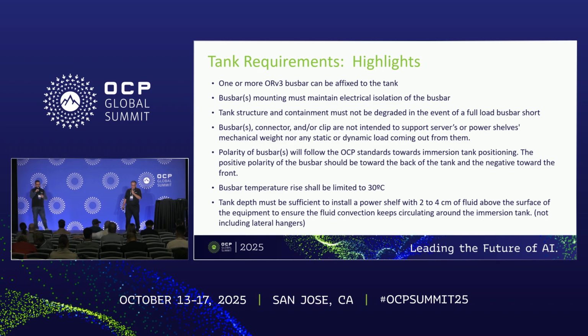Also worth mentioning, the busbar temperature rise has been tested in different environments where we pushed more than 100 kilowatts into those busbars, and there was no more than a 5 to 6 Celsius increase in temperature. We set a limit, agreed with the community, of 30 Celsius in the worst case scenario, which is still very manageable.